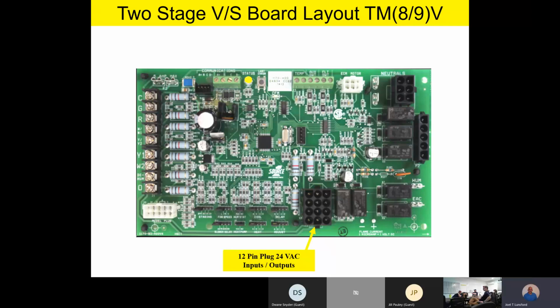Here's our 12-pin harness for 24-volt input-output. And this, again, will all be harnessed in from the factory. We just took the harness off so we could see it in the picture. But this is where we're going to have inputs and outputs to our pressure switches, over to our gas valve. All of our safety circuits will be harnessed in right here. So it's kind of a convenient place to know that your 24-volt inputs and outputs will be tied in right here. Typically they'll also have an output on this 12-pin harness for your flame sensor as well. So flame sensors and safety circuits and stuff like that will harness right in here in a nice convenient place where you can pull that harness apart, look it over, make sure the pins are clean, make sure the wires are in good and tight, and then snap it back on. So that's kind of a nice little convenient spot for all that.